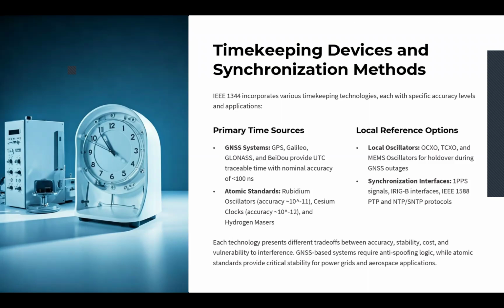For the primary time sources, we also have atomic clocks. They could be rubidium oscillators, cesium beam clocks, or hydrogen masers. The rubidium oscillator has an accuracy of around 10 to the power of minus 11, which is quite good, and cesium atomic clocks have an accuracy of 10 to the power of minus 12. But each technology has its own trade-offs in accuracy, stability, cost, and vulnerability. Now, besides the primary time source, we could have local reference options too.